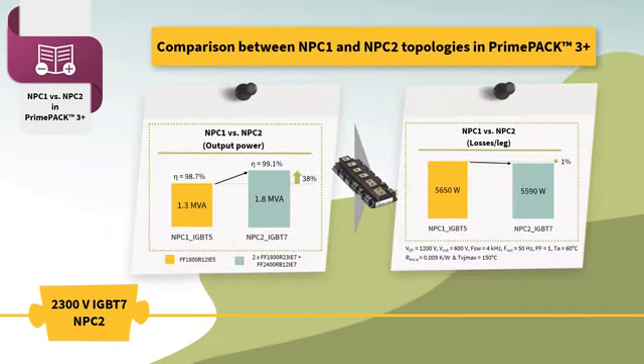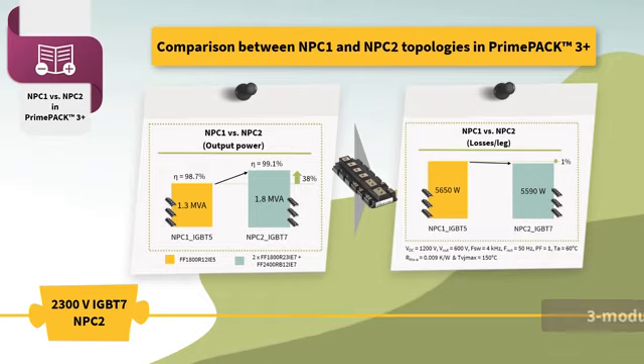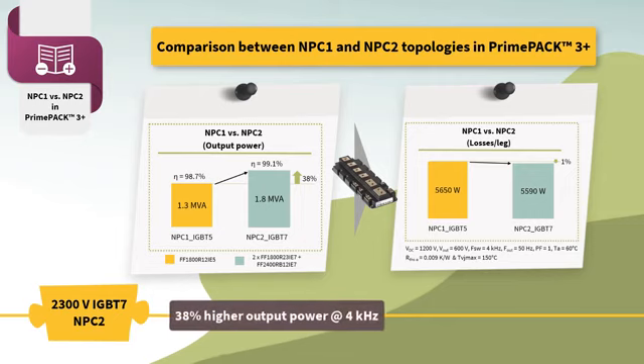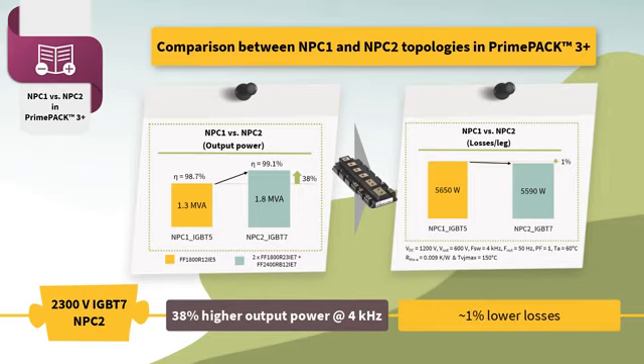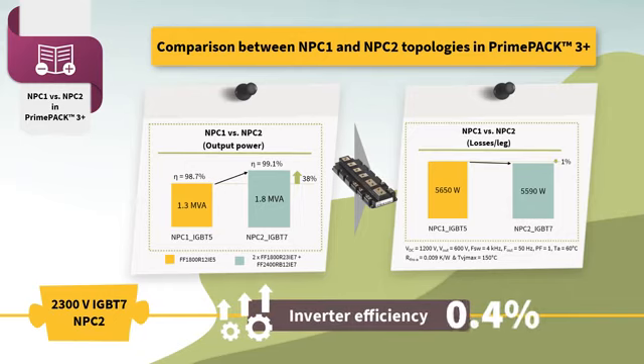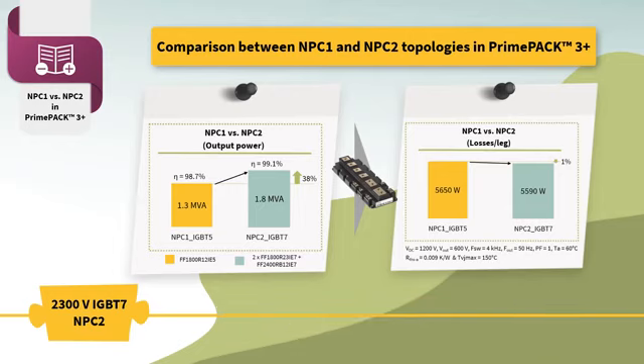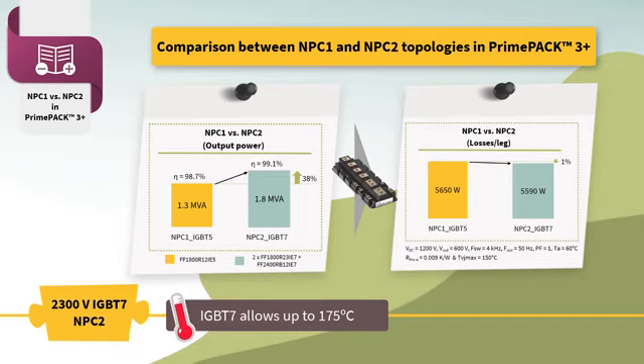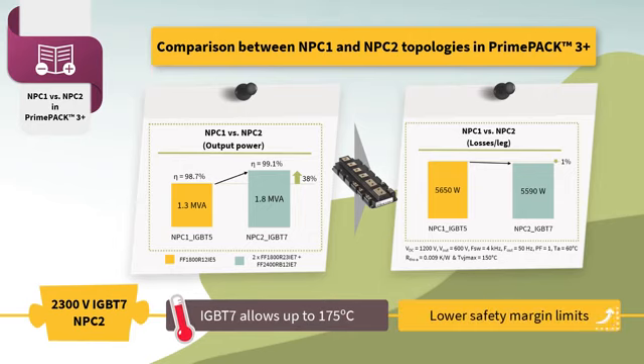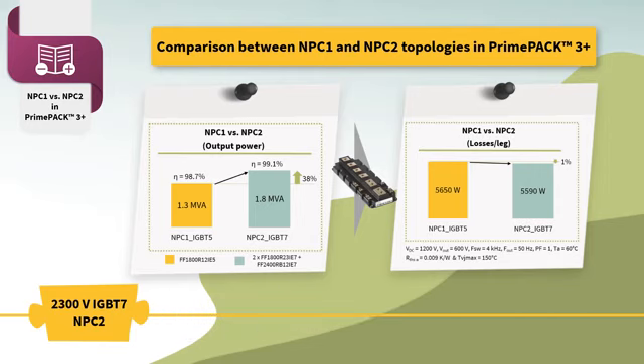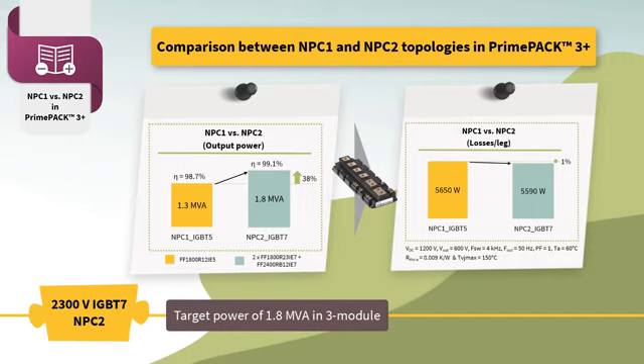Nowadays, the NPC1 topology is built with three PrimePACK 3 modules. So, for a fair comparison between NPC1 and NPC2 topologies, a 3-module solution is considered. An NPC2 topology enables the designer to reach 38% higher output power at a 4 kHz switching frequency operation with almost 1% lower losses. This further improves the inverter's efficiency by 0.4%, which is very impressive. As mentioned, IGBT-7 chip technology allows up to 175 degrees, enabling the increase of the inverter's power which can be operated within lower safety margin limits. Furthermore, it is possible to reach a target power of 1.8 MVA in a 3-module configuration and of 1.3 MVA in a 2-module configuration.